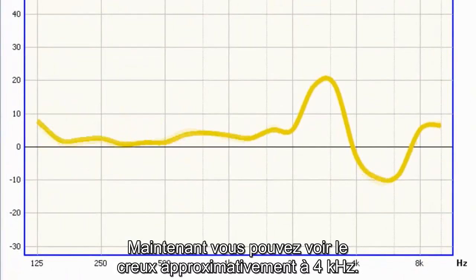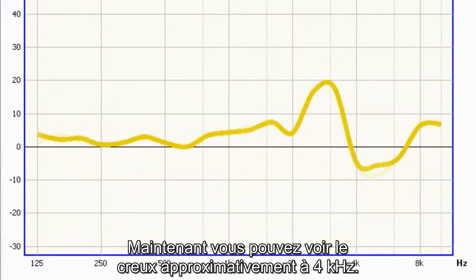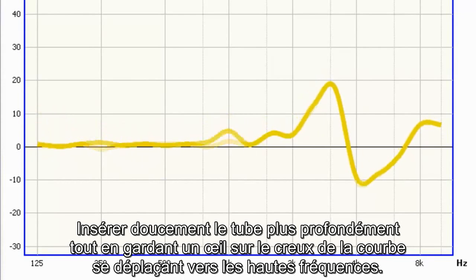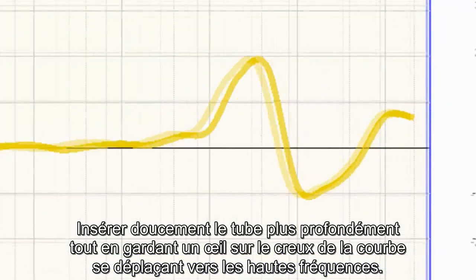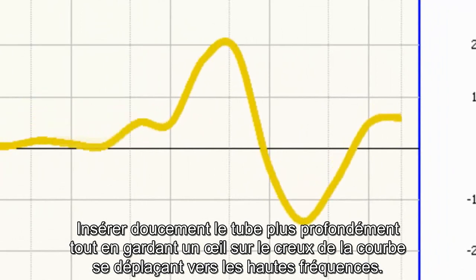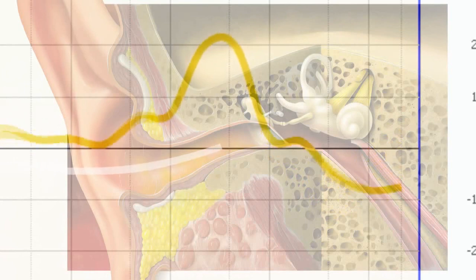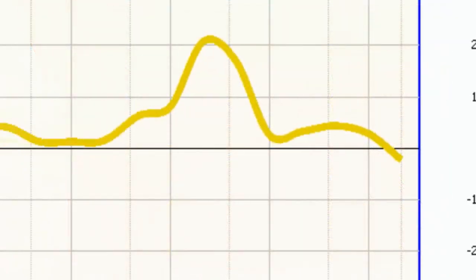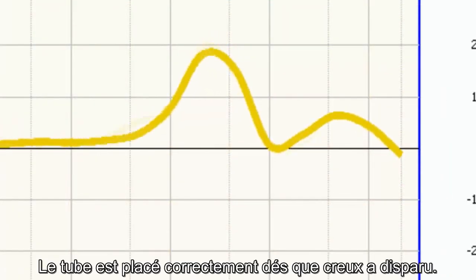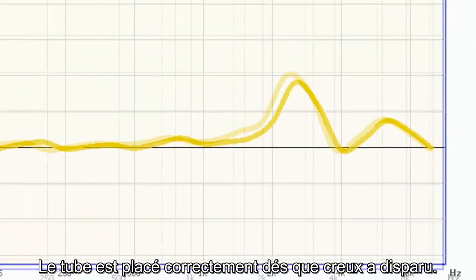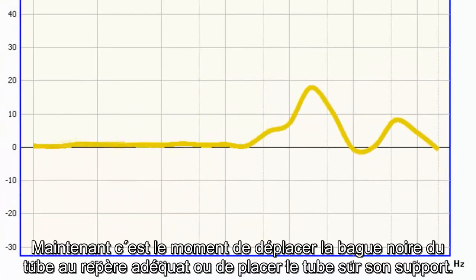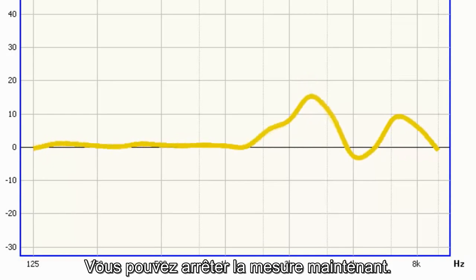Now you will see a notch at approximately 4 kHz. Gently insert the probe tube deeper while keeping an eye on the notch, which is moving towards higher frequencies. The probe tube is located correctly as soon as the notch is no longer dragging the measurement curve down at 10 kHz. Now's the time to move the black ring into position or attach the probe tube onto the probe tube support. You can stop the measurement now.